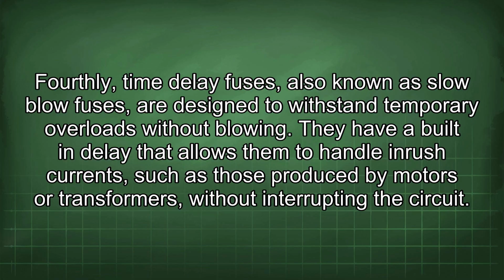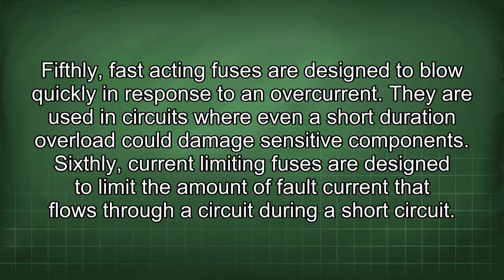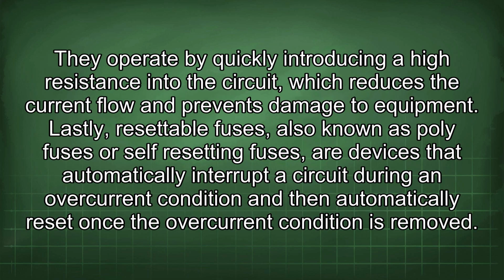They have a built-in delay that allows them to handle inrush currents, such as those produced by motors or transformers, without interrupting the circuit. Fifthly, fast-acting fuses are designed to blow quickly in response to an overcurrent. They are used in circuits where even a short duration overload could damage sensitive components. Sixthly, current-limiting fuses are designed to limit the amount of fault current that flows through a circuit during a short circuit.